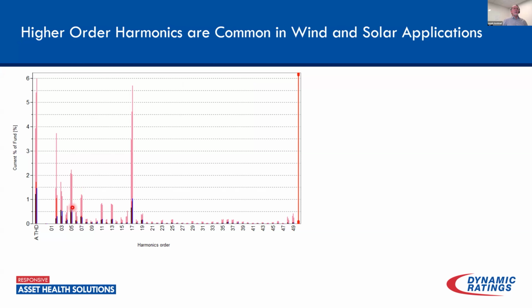And we do see that here, but in a lot of renewable applications, we also see a lot of higher order harmonics. Here we're looking at basically the predominant component in the harmonics, which is a 17th harmonic. And when you look at the CIGRE bulletin on asset reliability, they're pretty much recommending that you need to monitor harmonics because we could be seeing harmonics out to the 50th when it comes to these renewable applications.